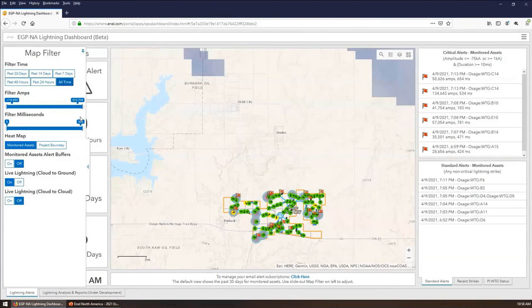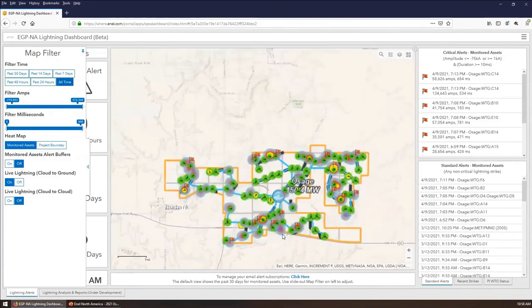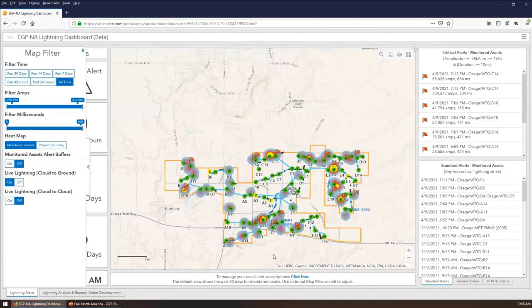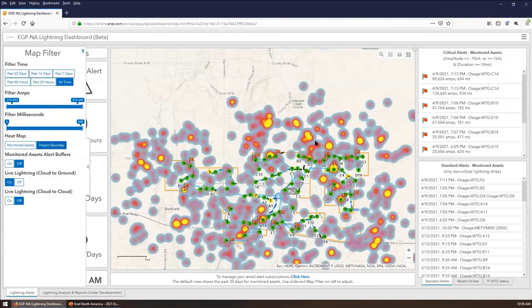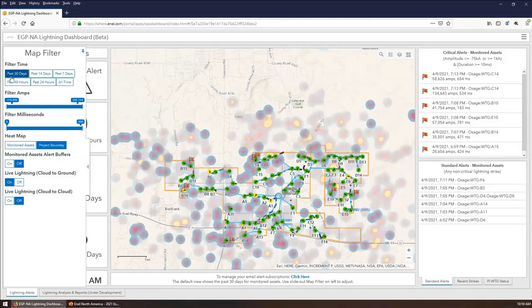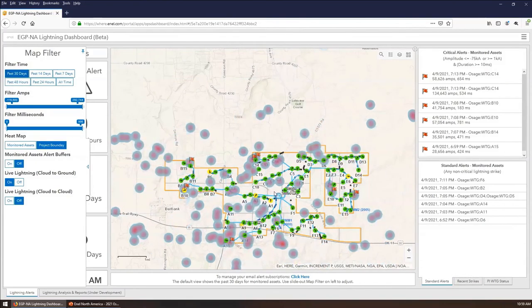Other things we can do here are apply various map filters to better look for trends. We can filter by time—the default is 30 days—but we can flip this on to 'all time,' which is when we started recording lightning strikes around last July. Right away, you can see trends showing that certain wind turbines are more susceptible to being struck than others. This gives our operations crew the information necessary to optimize maintenance procedures—inspecting the more frequently struck ones more often and conducting less frequent inspections on those less impacted by lightning. We can also change the heat map from our monitored assets to within two kilometers of our project boundary, giving more insight into lightning activity during a particular storm.